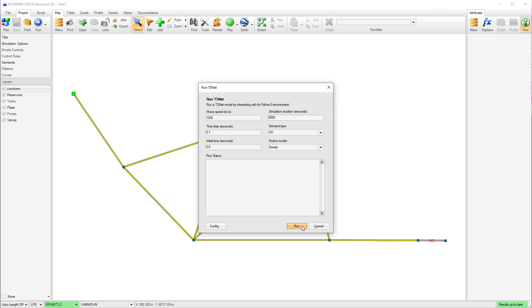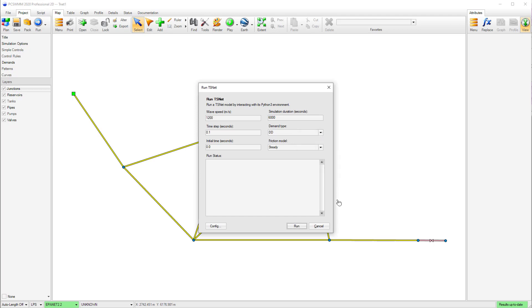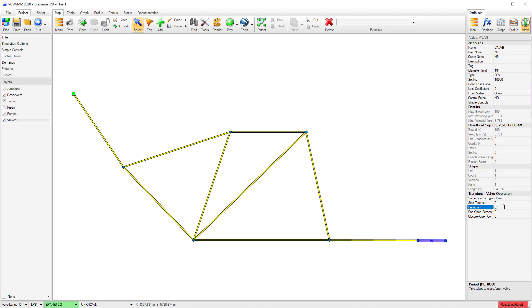PC Swim will prompt additional user-defined attributes to be created. I will click yes to create these attributes. Now when I click on the valve, you will see that there are additional attributes to set up the transient valve operation parameters. For this simulation, I will set the surge source to closed, the period to 0.1, and the closure to 1.